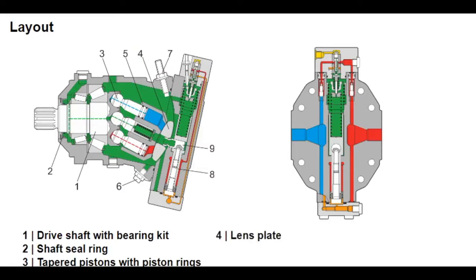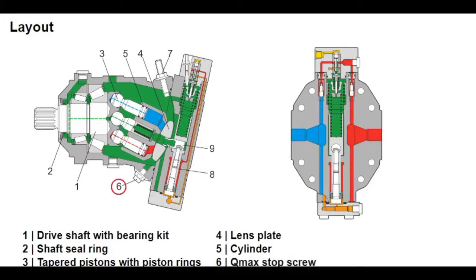Due to the bent axis design, torque is produced directly on the driveshaft. The pistons exert minimal lateral force on the cylinder, which reduces wear, increases efficiency, and improves starting torque. The maximum swivel angle, and thereby the maximum output torque, can be limited with a Q-max stop screw (6). The minimum swivel angle, and thereby the maximum output speed, can be set by the Q-min stop screw (7).